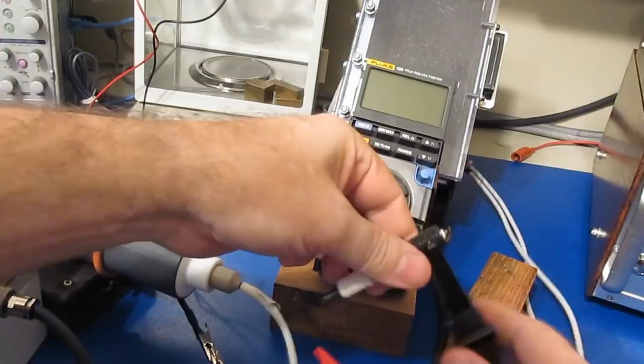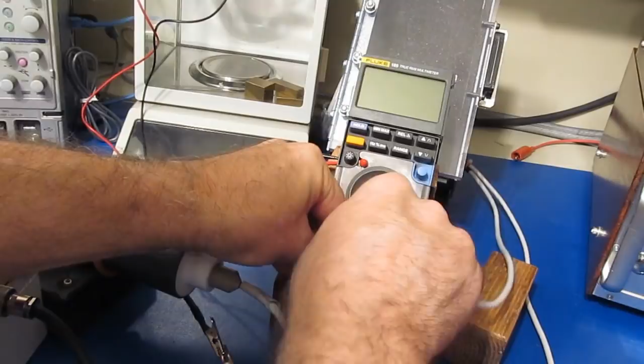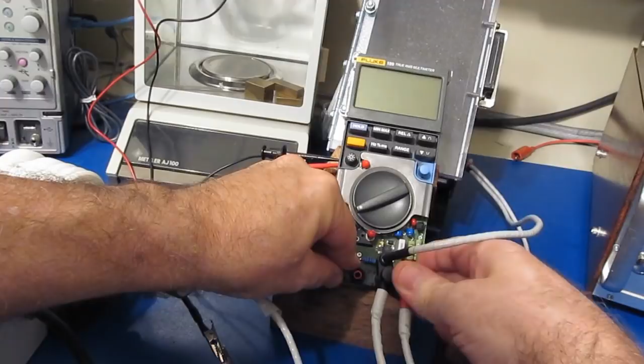This will be an 8000 volt peak transient with a 2 ohm source impedance. Again, we'll be applying 5 transients with each mode of the meter, and then I'll perform a functional test on it to check for any damage. Right now the meter is running off an external battery pack, and I want to make sure we don't have any kind of current loop. Alright, let's go ahead.